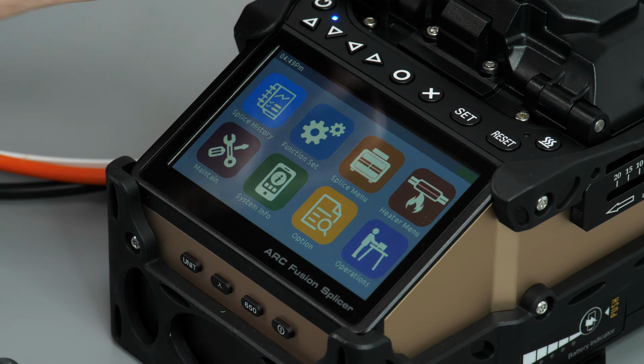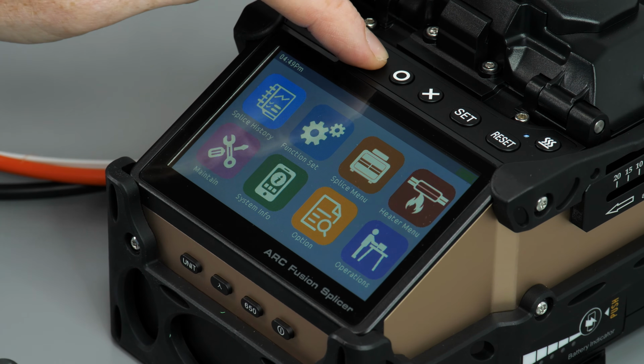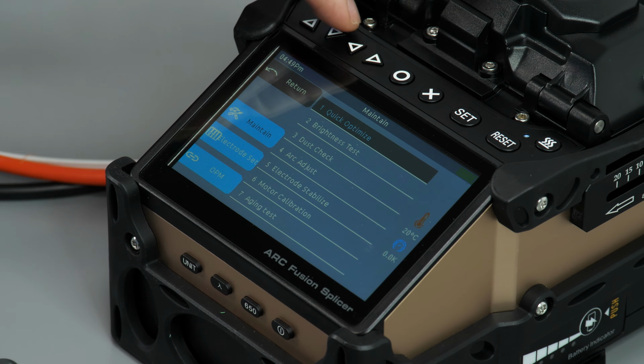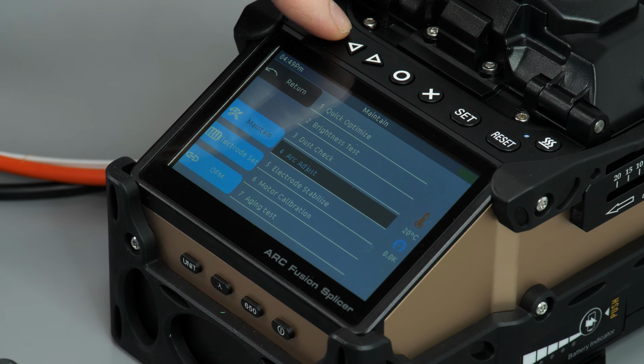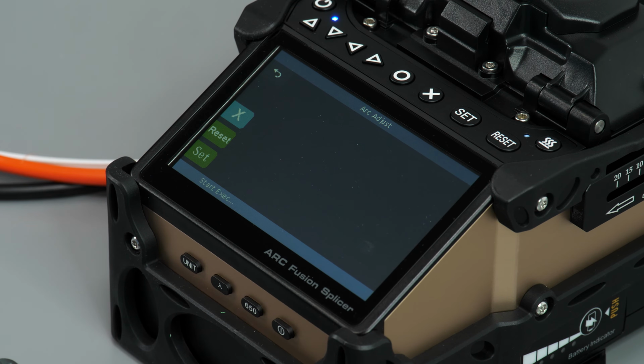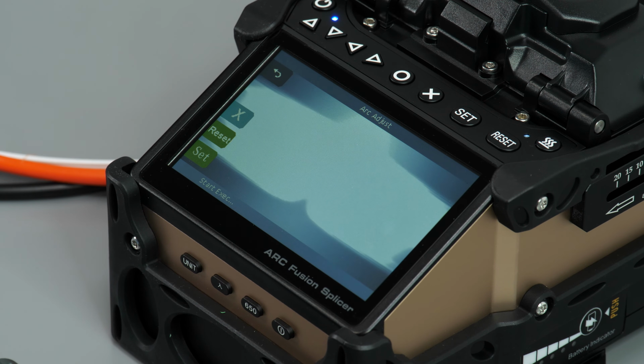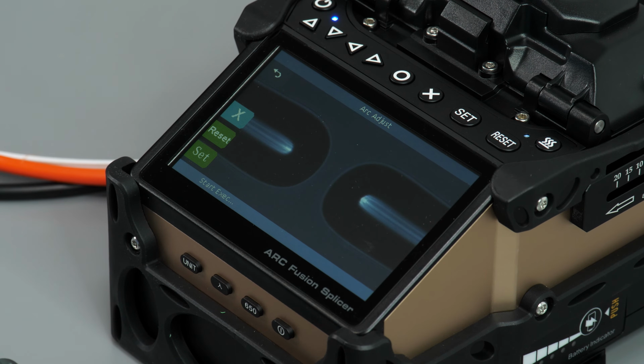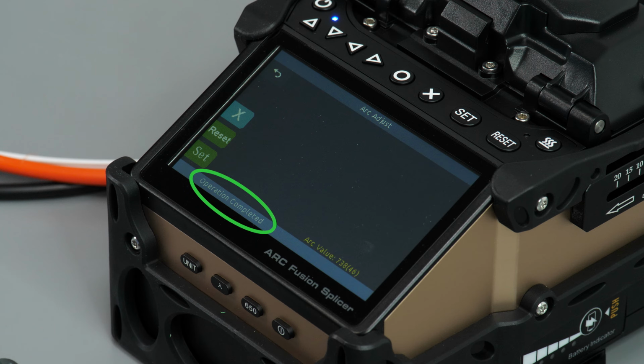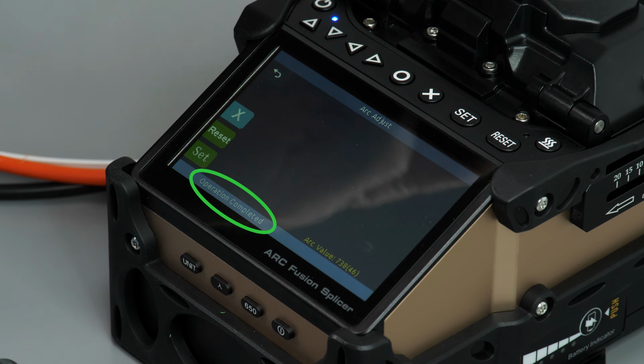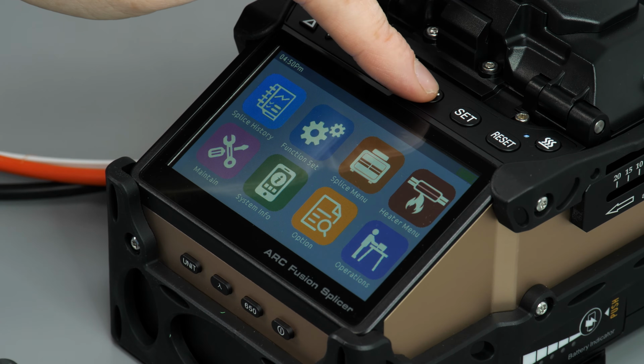To start the calibration procedure, enter the device menu, select the maintenance submenu, and enable the arc adjust function. Calibration is started with the set button on the housing or the welding machine screen. The entire process takes a few seconds. The welding machine generates an electric arc, melting the fibers. The device analyzes the behavior of the fibers at a given arc power and makes any necessary adjustments. The end of the procedure is confirmed by a relevant message on the screen. Now you can start the actual welding.